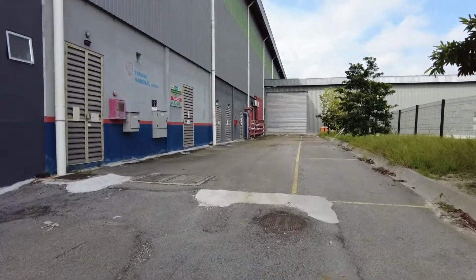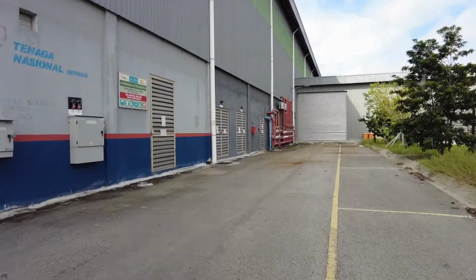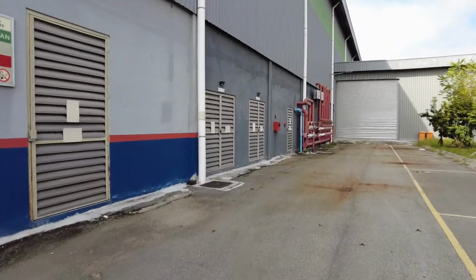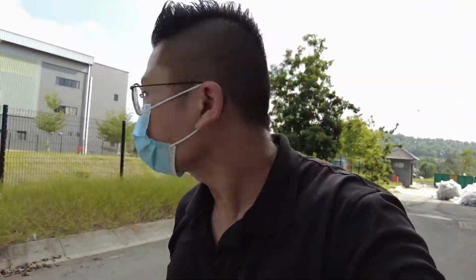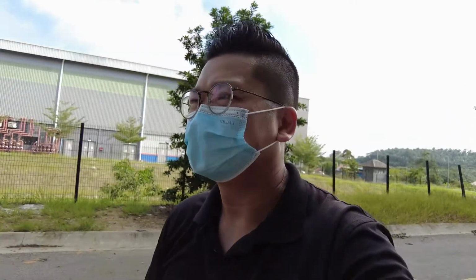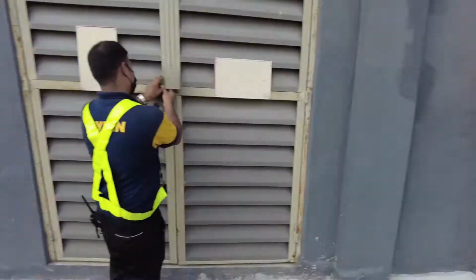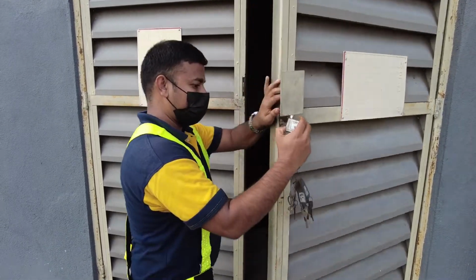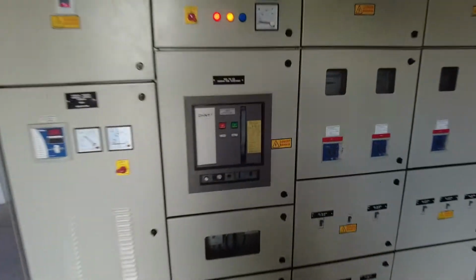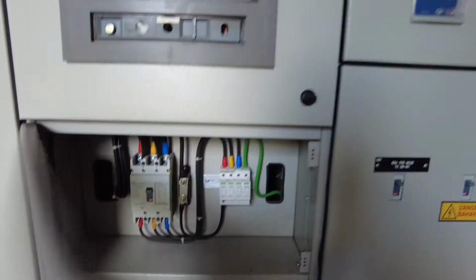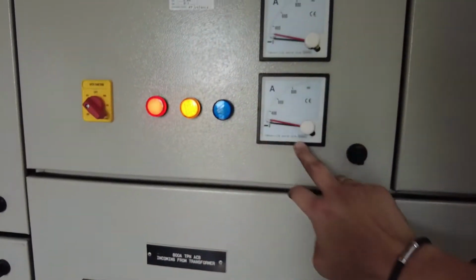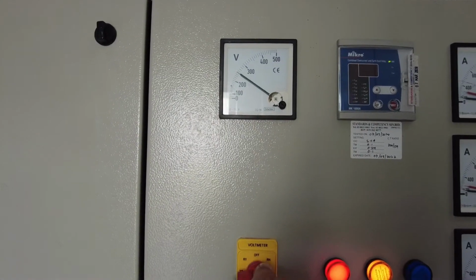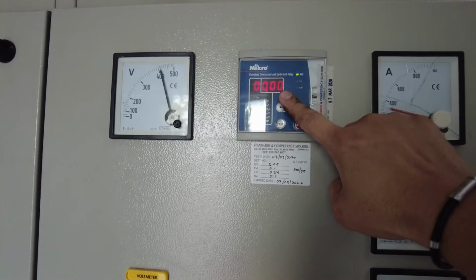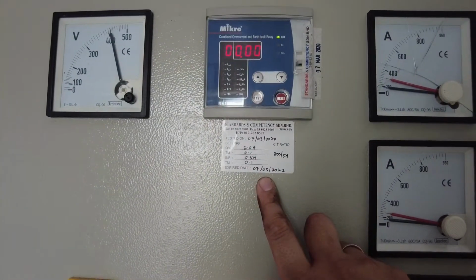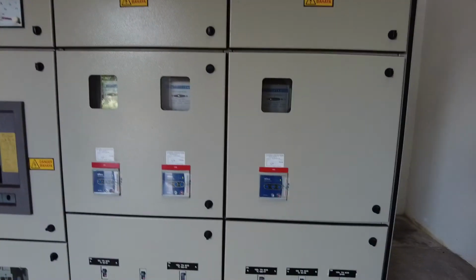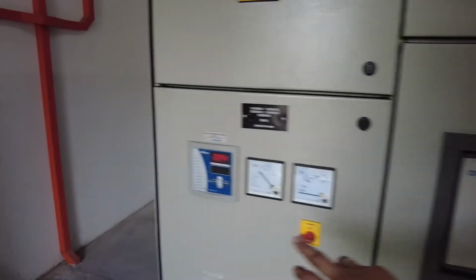So now we are on the way to the HV room, transformer room and LV room. Okay, this is the LV room. Take a look at the surge arrestor. Okay. ACB okay, on. Voltage okay. Protection relay in function. Calibration is 7 March 2022. The rest of the relay also no tripping. In good condition.